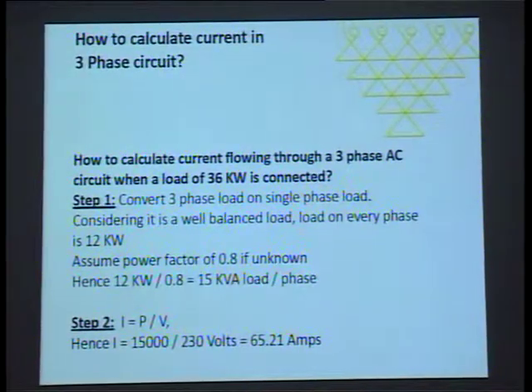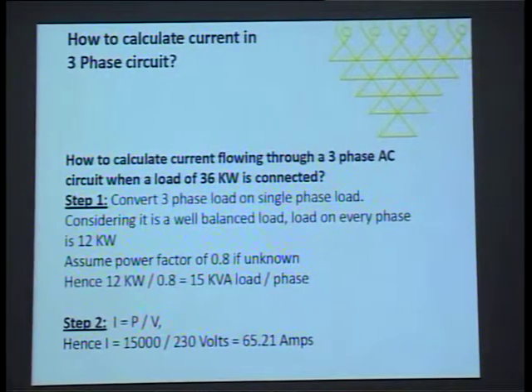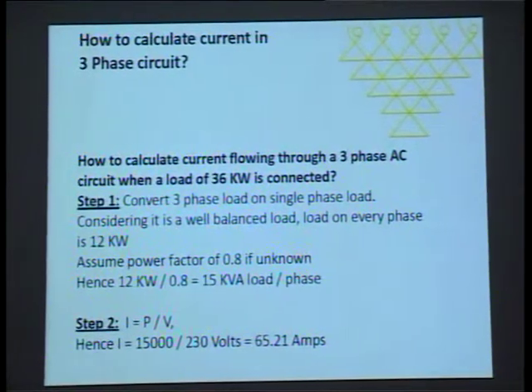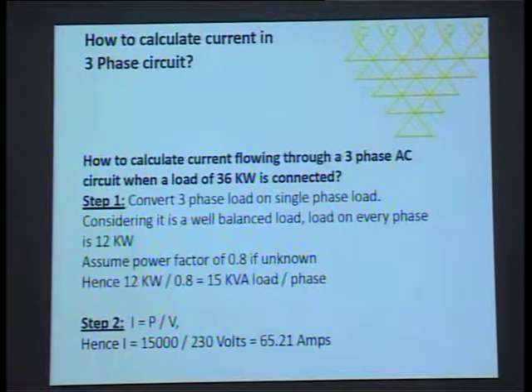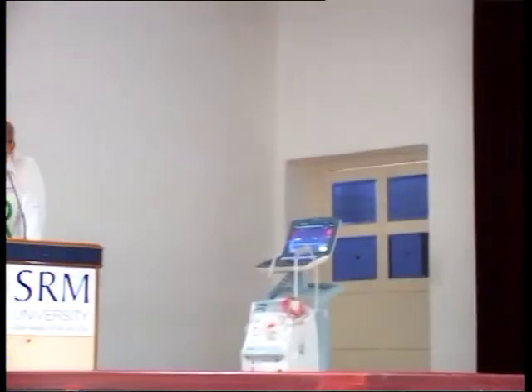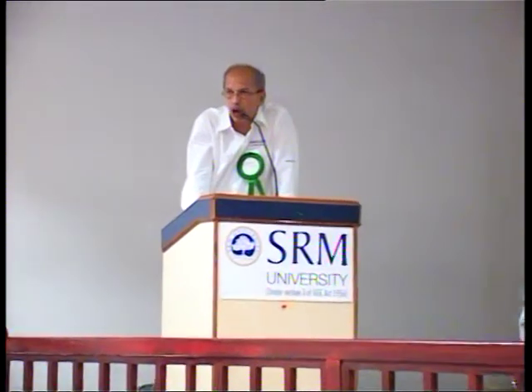Can you calculate the current flowing through each phase? Yeah. The very simple technique is you can divide this three-phase load into per phase. For example, if the equipment is designed to consume 36 kilowatts, then if all the phases are balanced properly, there will be a load of say 12 kilowatts on every phase. Now you divide it by the power factor. If you don't know the power factor, use the figure of 0.8. So 36 kilowatt for three phase means 12 kilowatts per phase, and when you divide this 12 kilowatts by the power factor, you reach a figure of 15 kVA. And once you divide this 15 kVA by the phase voltage of 230 volts, you arrive at the figure of 65 amperes.